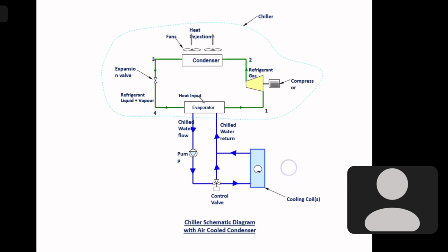And the water coming out from the cooling coil gets a little warmer, because it has cooled the return air. So we take that warmer chilled water back to the evaporator, recool it, and supply it back to the cooling coil again. This is done by a pump, which is called the chilled water pump, in the chilled water circuit.